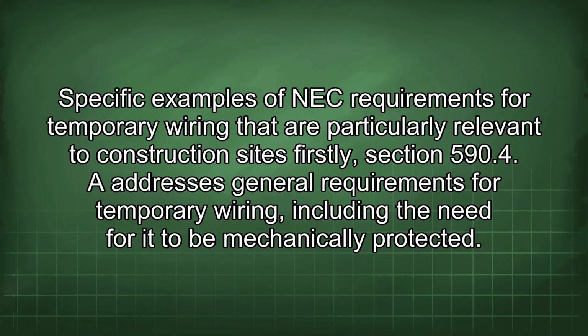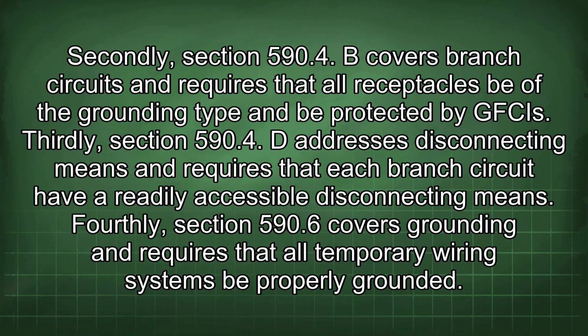Specific examples of NEC requirements for temporary wiring that are particularly relevant to construction sites. Firstly, Section 590.4 addresses general requirements for temporary wiring, including the need for it to be mechanically protected. Secondly, Section 590.4 B covers branch circuits and requires that all receptacles be of the grounding type and be protected by GFCIs. Thirdly, Section 590.4 D addresses disconnecting means and requires that each branch circuit have a readily accessible disconnecting means. Fourthly, Section 590.6 covers grounding and requires that all temporary wiring systems be properly grounded.